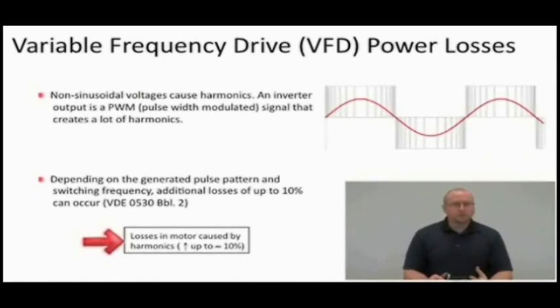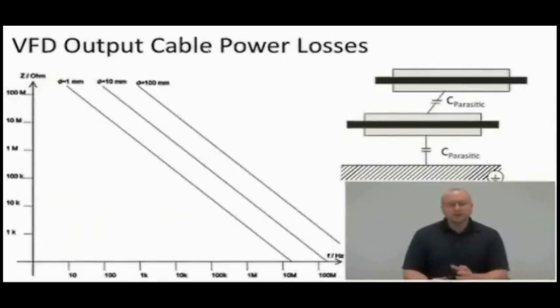What an AC induction motor wants to see is a perfectly sinusoidal voltage. It wants to see that sine wave signal that you're used to seeing for voltage. With these pulses, it creates harmonics, and these harmonics can add losses into your system. And it depends on the pulse signal. It also depends on your switching frequency and pattern. But we'll talk about that in a little bit when we talk about the motor. There's another potential power loss in the cable going from your VFD to the motor, and that's parasitic capacitance.